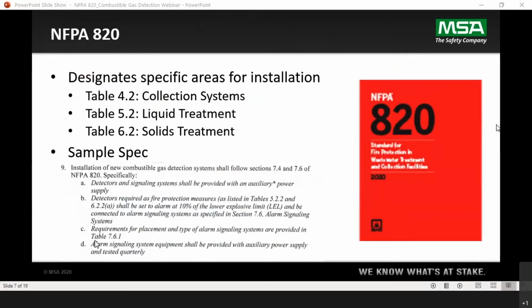If you dig deeper, and today I won't spend a lot of detail on it, as it's a summary review, there are basically 3 tables called out: tables 4.2, 5.2, and 6.2. They break it up into collection systems and the different types of treatment, either liquid treatment or solid treatment. If you go deeper into the standard, you'll see things like scum pits, sludge tanks, thickeners, and clarifiers. By their unit operation and function, they require CGD, or combustible gas detection. It's also typically noted that it would be enclosed, so indoor buildings will more likely require combustible gas detectors.